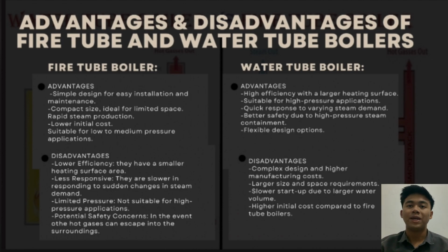Disadvantages. Complex design: they are more complex in design and construction, which can make them costly to manufacture, install and maintain. Large size: water tube boilers are large and may require more space. Slow startup: they take longer to start producing steam due to their large water volume. Higher initial cost: typically, water tube boilers have a high initial cost compared to fire tube boilers.